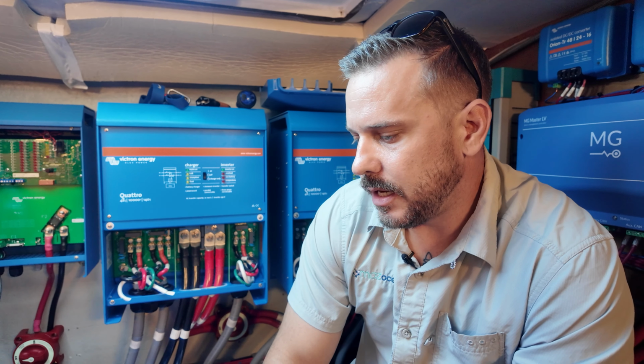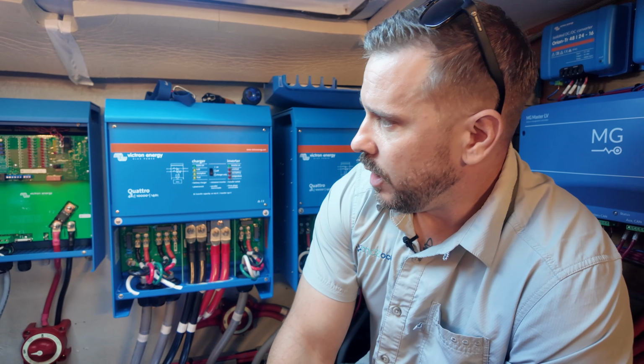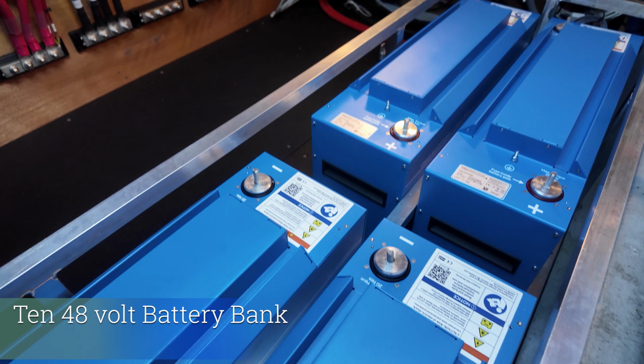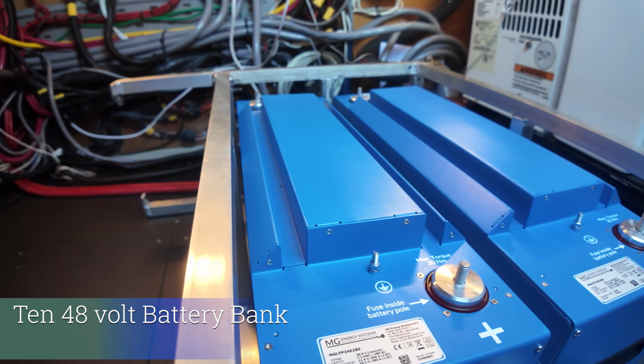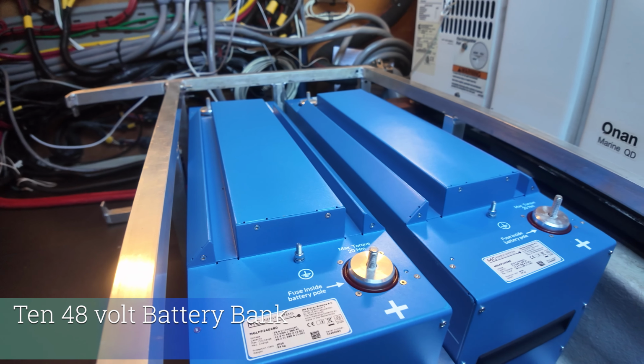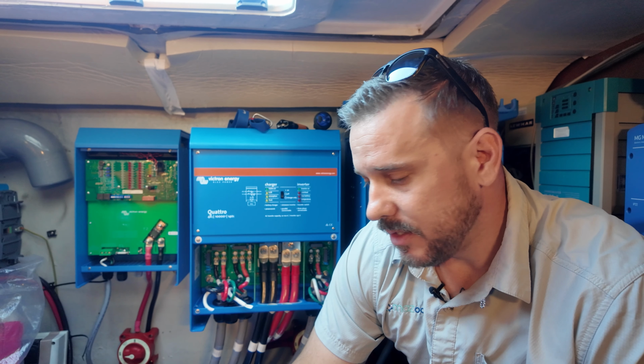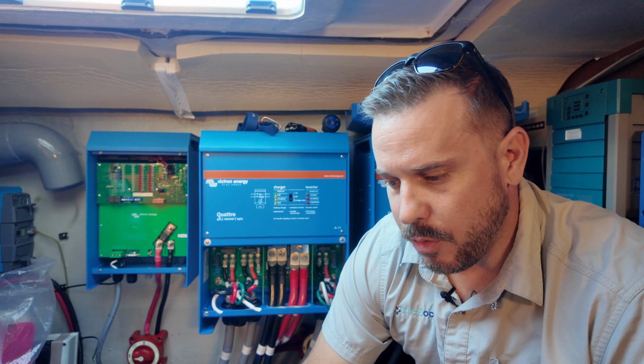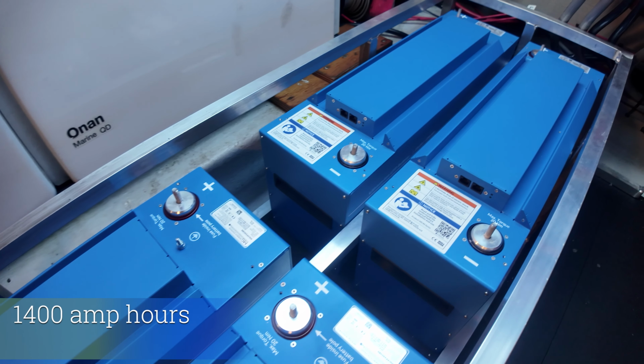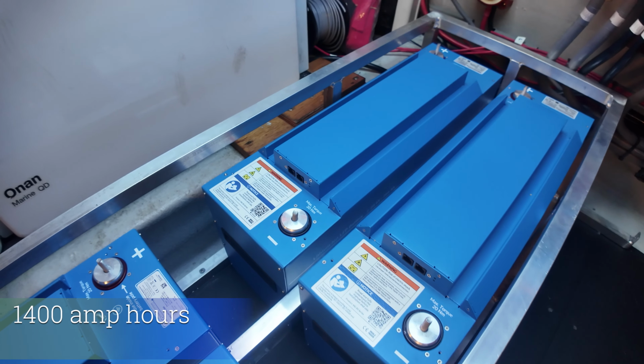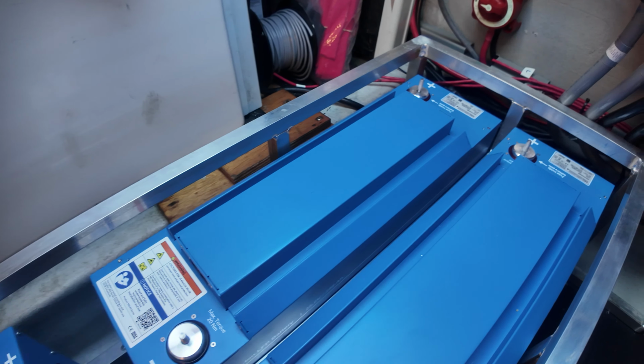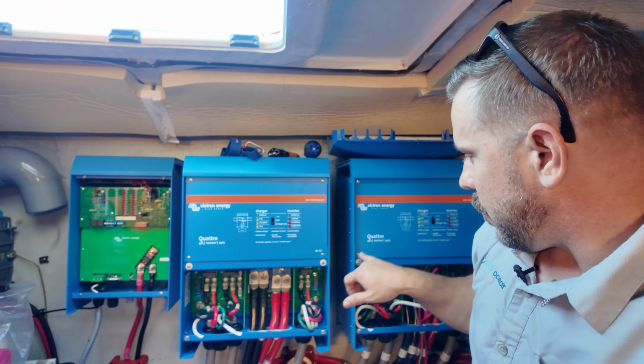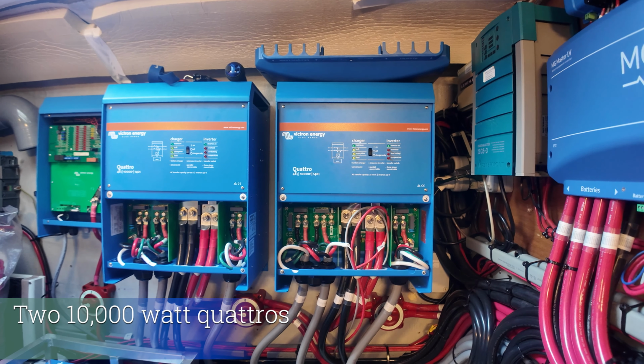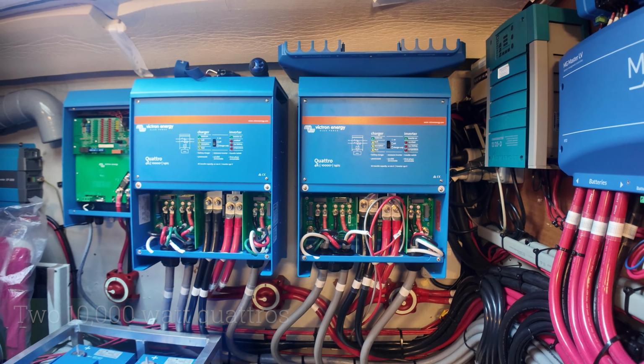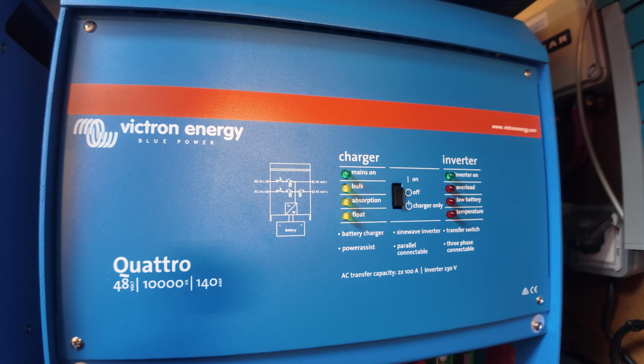So what we have to start with is a 10 battery bank for our 48 volts. We've got 5 batteries wired in series sets of 2s to give us 48 volt. So what we end up with is 1400 amp hours of capacity specifically for our 48 volt system. Additionally, we have two 10,000 watt Quattros here, which each provide 140 amp of charge to the 48 volt bank, as well as 20,000 VA of inversion.